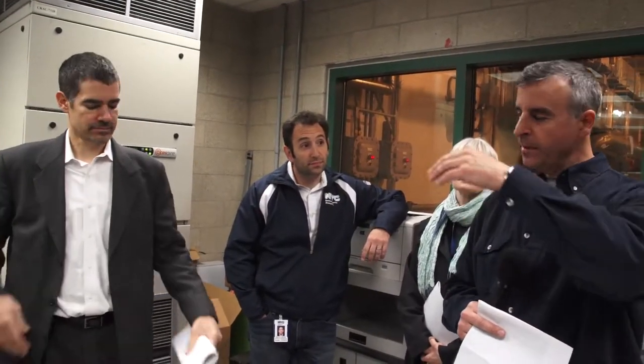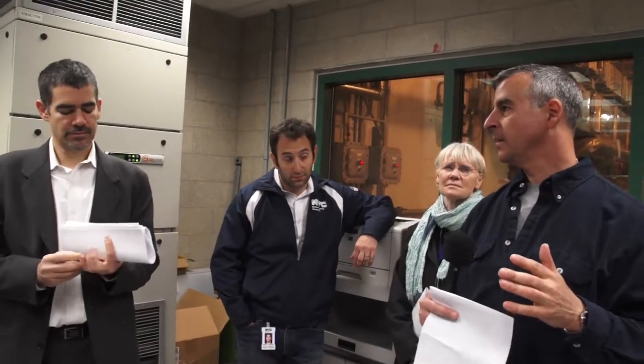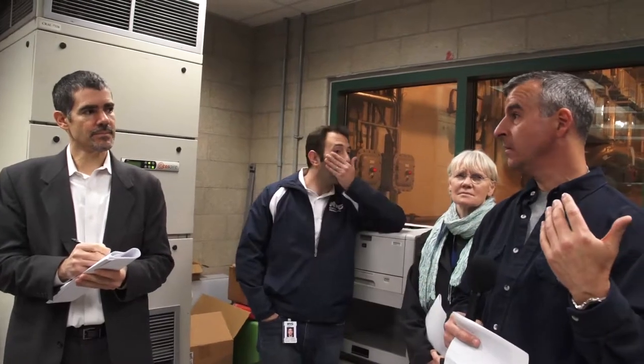So this facility has 48 flushing gates, 12 per tank, okay? They open in series, and it uses wave action to clean the bottom of the tank. It flushes into a central channel, that channel then goes into the wet well and gets pumped out. So it does a very efficient job of moving the grit into, yeah, there you go, Kevin's got a photo. It does a very efficient job of getting it to the wet well.